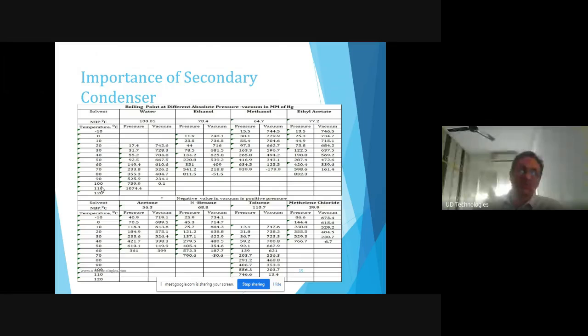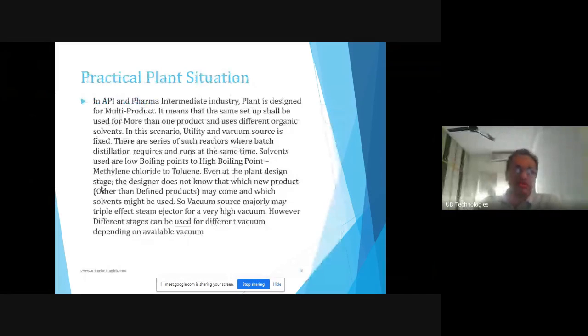Now we'll come to the practical plant situation. Basically, we have to understand why vacuum, and how vacuum control is used to reduce solvent loss. In the pharma API industry, a plant is designed for multiple products. In the same setup of glass-lined reactor to condenser to receiver, they design for different products and use the same plant. For different products they use different organic solvents. In this scenario the utility and vacuum source are fixed when you design the plant.